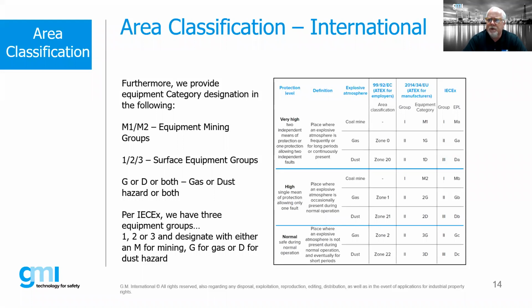On the top of those columns there, you'll see 99/92/EC. That's ATEX for employers. That has to do with our area classification. So it is a responsibility under the ATEX directive for the clients to make a determination as to what areas within their process facility should be classified. And again, we use the 60079 standards. The categories are what you see on the right-hand side at the very top. You'll also see 2014/34/EU. That's ATEX for manufacturers. So once we've determined our area classification, then we have to determine, is the product suitable for it, and how are we going to mark this product?